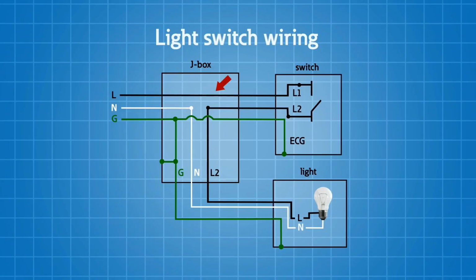If you think about how we wired residential homes or any types of structures when we came down to a light switch, what did we do? We brought one set of conductors, and that was our hot conductor. And we brought an equipment grounding conductor as well. And we did not bring a neutral. When we had a standard light switch, that was perfectly fine because we're just breaking one conductor.